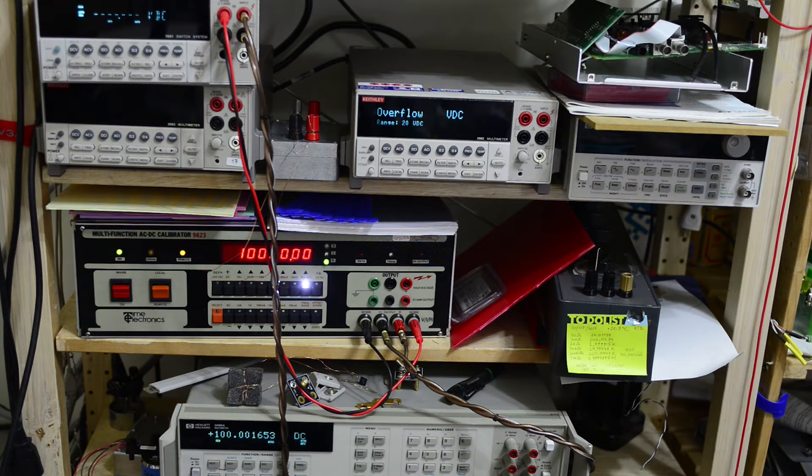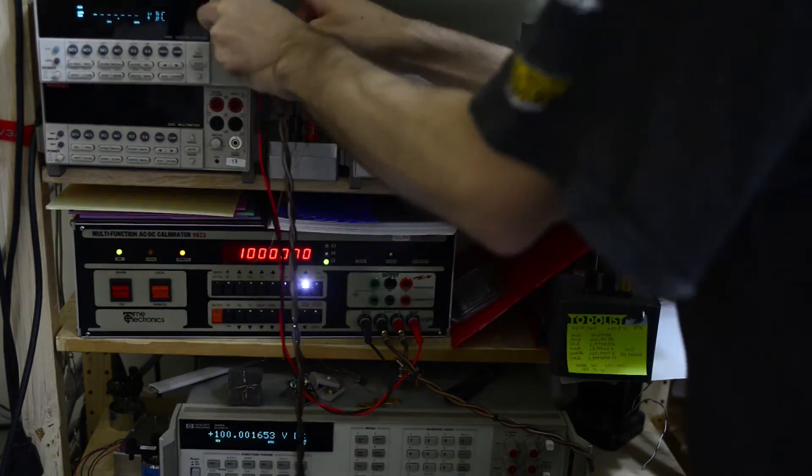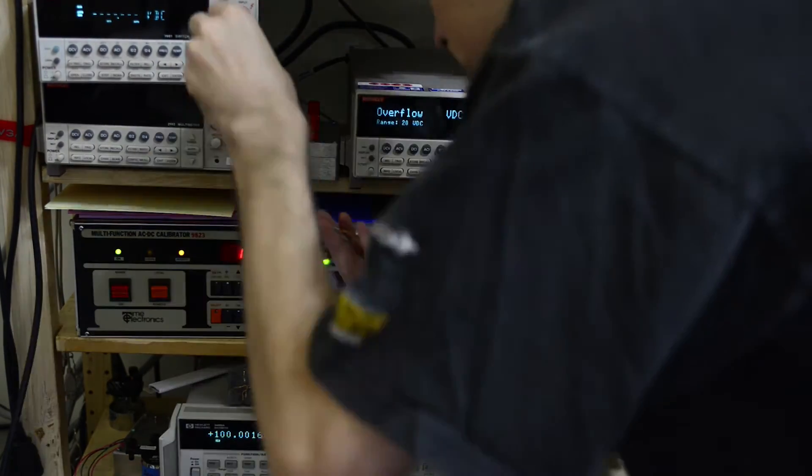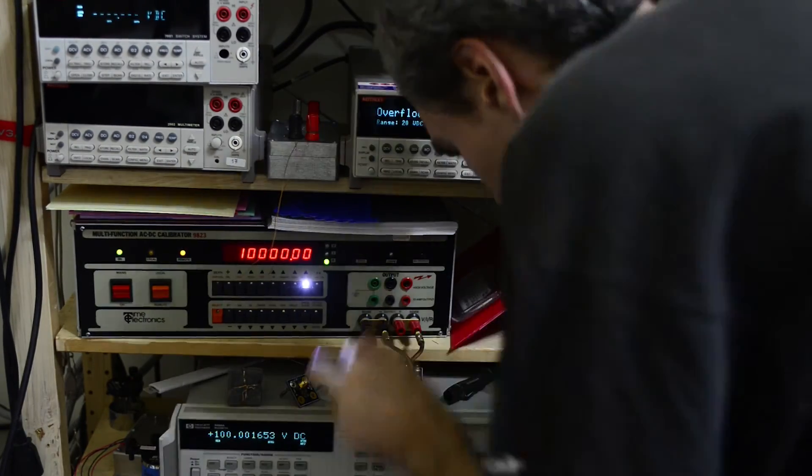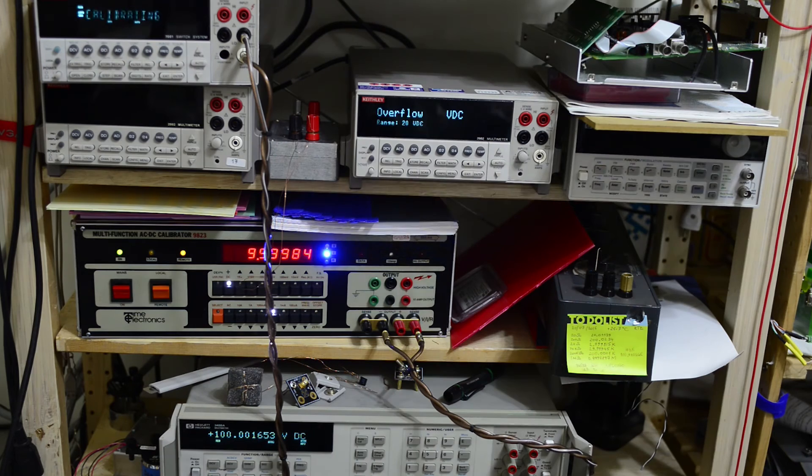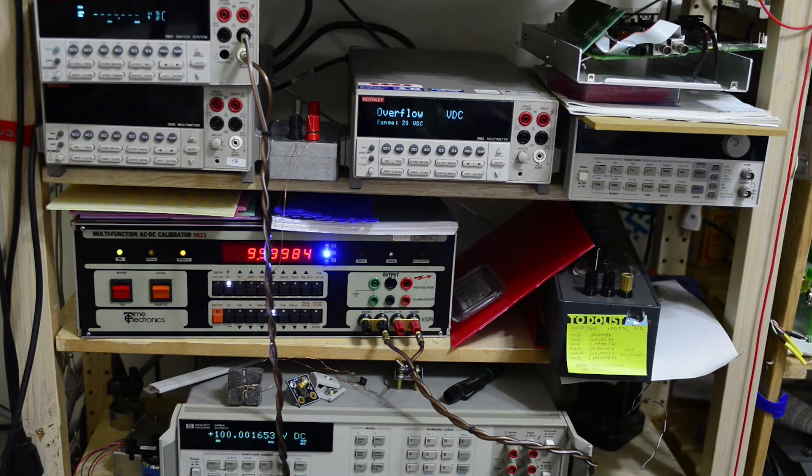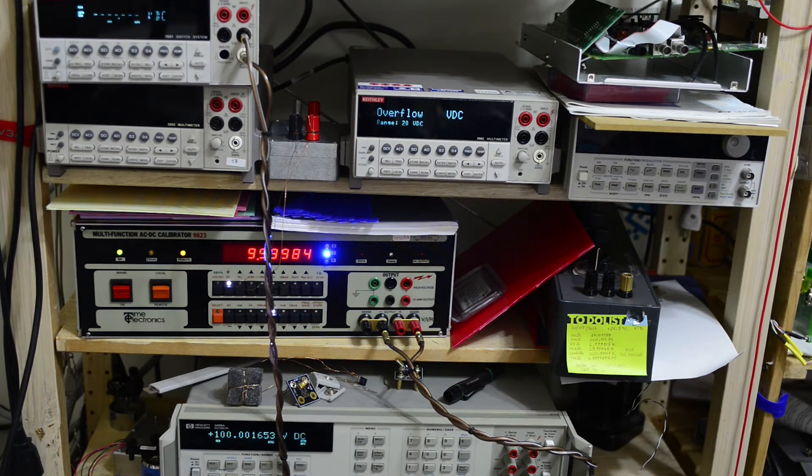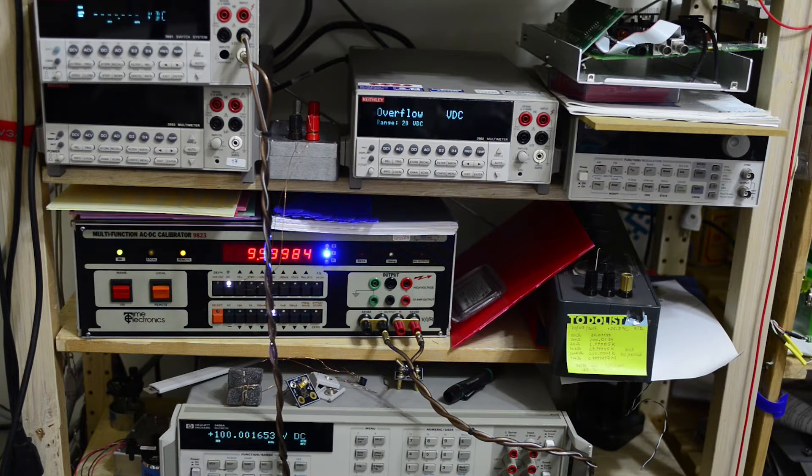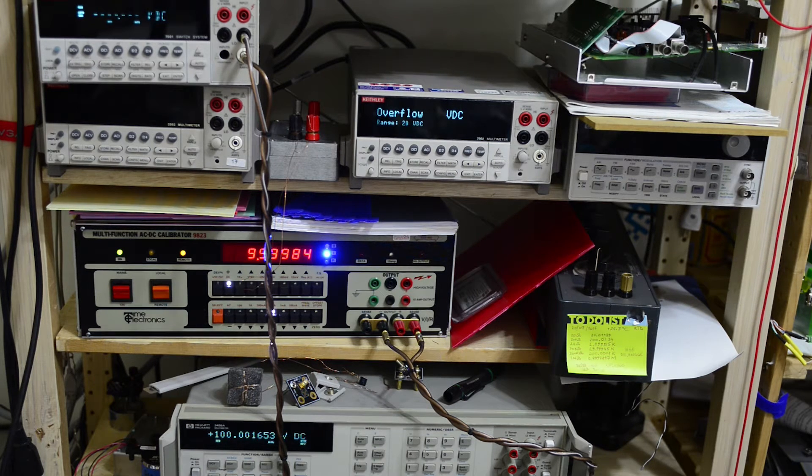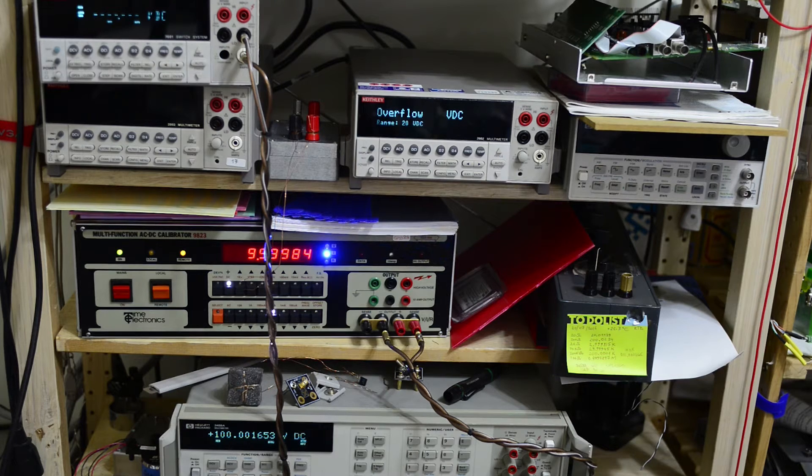And now we need to switch terminals again for current calibration, which is 10 milliamp, 100 milliamp, and 1 amp DC. This just takes a minute or so and we are almost done.